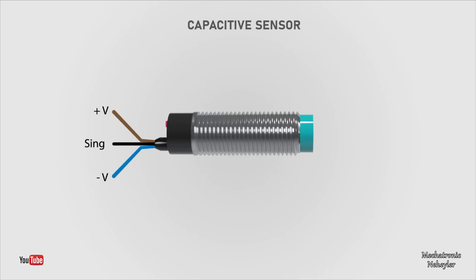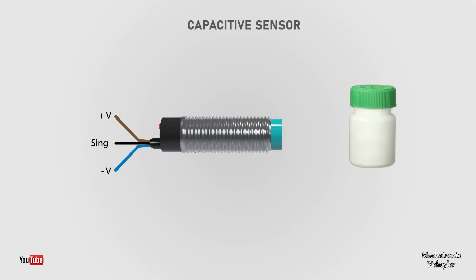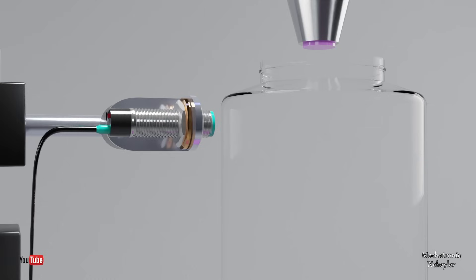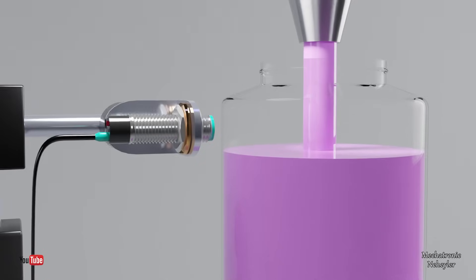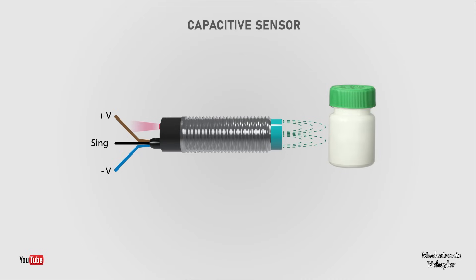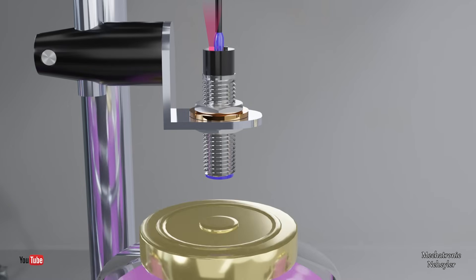The capacitive sensor has an external appearance very similar to the inductive sensor, since it consists of the same parts. But the difference is that it not only detects ferrous metal objects — it can also detect any other objects like plastic, mineral, glass, wood, paper, liquid, etc. Capacitive proximity sensors react to alterations in electrostatic fields, based on dielectric principles of capacitance to establish a detection field near the face of the sensor. It must be remembered that inductive sensors react to changes in magnetic fields.